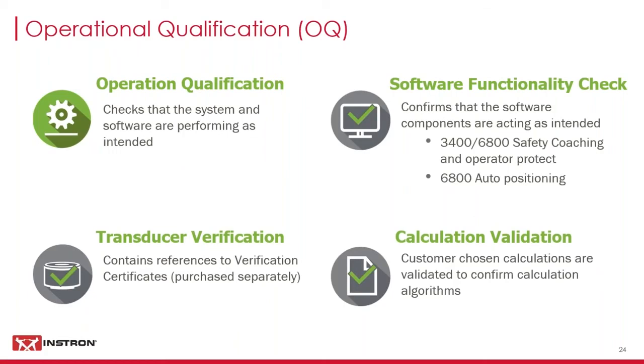Instron verifications and IQOQ validation work together to ensure that the system is doing what it's supposed to and that the data coming from the transducers is accurate and reliable. The OQ contains references to the Instron transducer verification certificates. The bulk of the OQ is the software functionality check. In this section, the most common functions and features of the software are checked to confirm that they are acting as intended. As new features are released, the document package is updated accordingly.